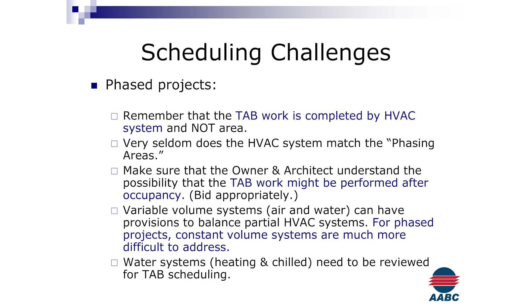I got the high sign for 10 minutes, so I'll move along. Remember that TAB work is completed by HVAC system, not area. We cannot go into a portion of a system, balance 8 of 20 outlets, and expect that balance to hold when we come back to do the next 20. You have to balance an entire system at once. That doesn't mean the balancer shouldn't have time to rebalance systems as each phase completes, if that's called out in the phasing of the bid. That's another better practice: make sure TAB work is completed by system, not area.